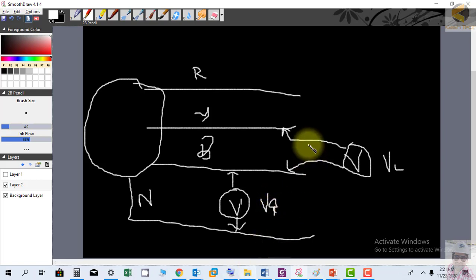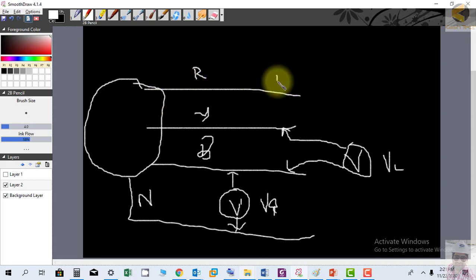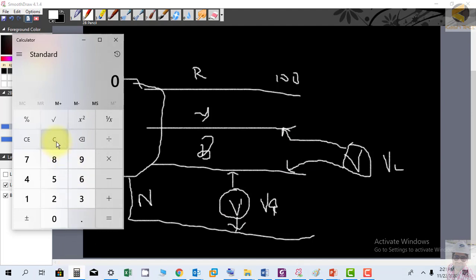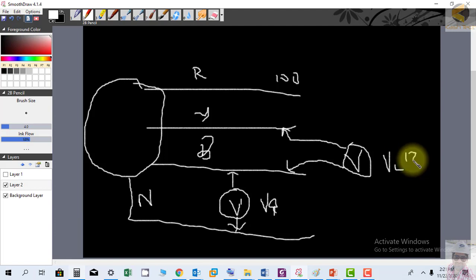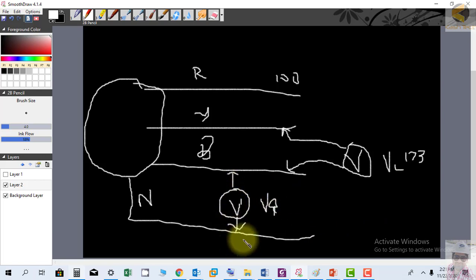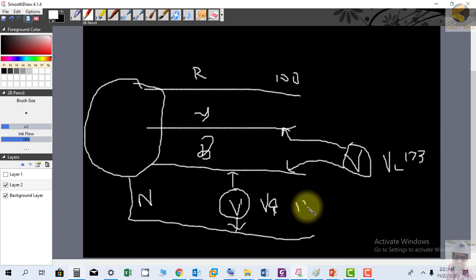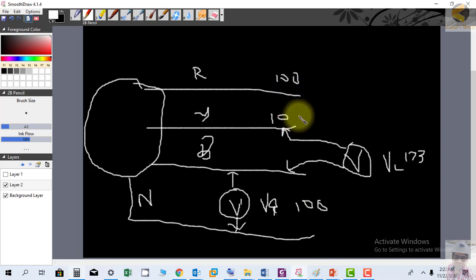If the generator is producing 100 volts phase voltage, and you measure between two phases, you get 100 × 1.732 = 173 volts — that is the line voltage. If you measure between a phase and neutral (which is at zero potential), the voltmeter reads 100 volts.